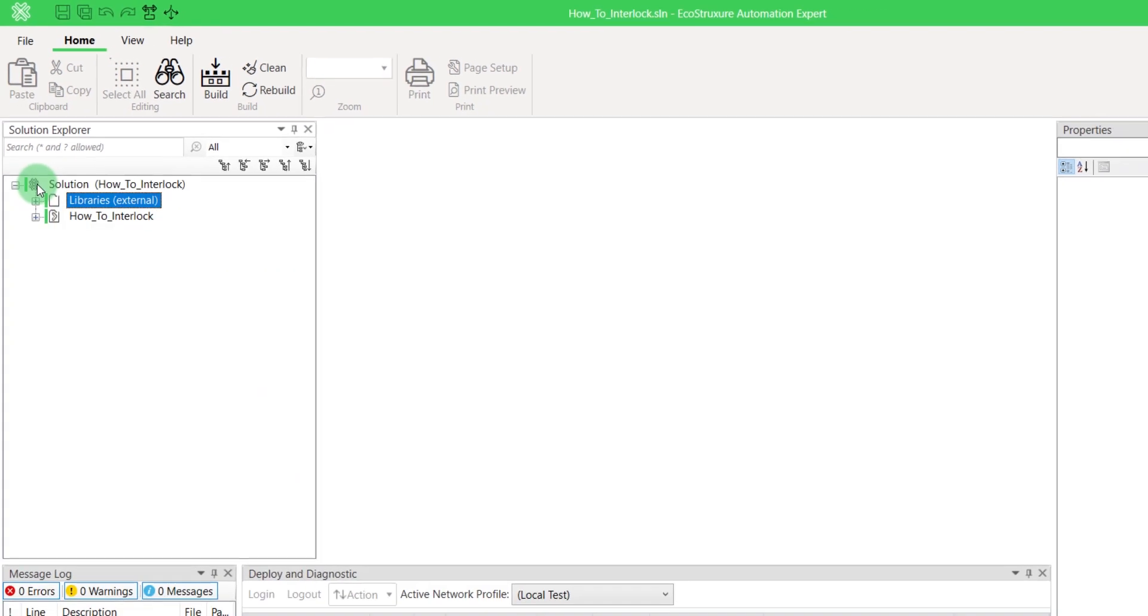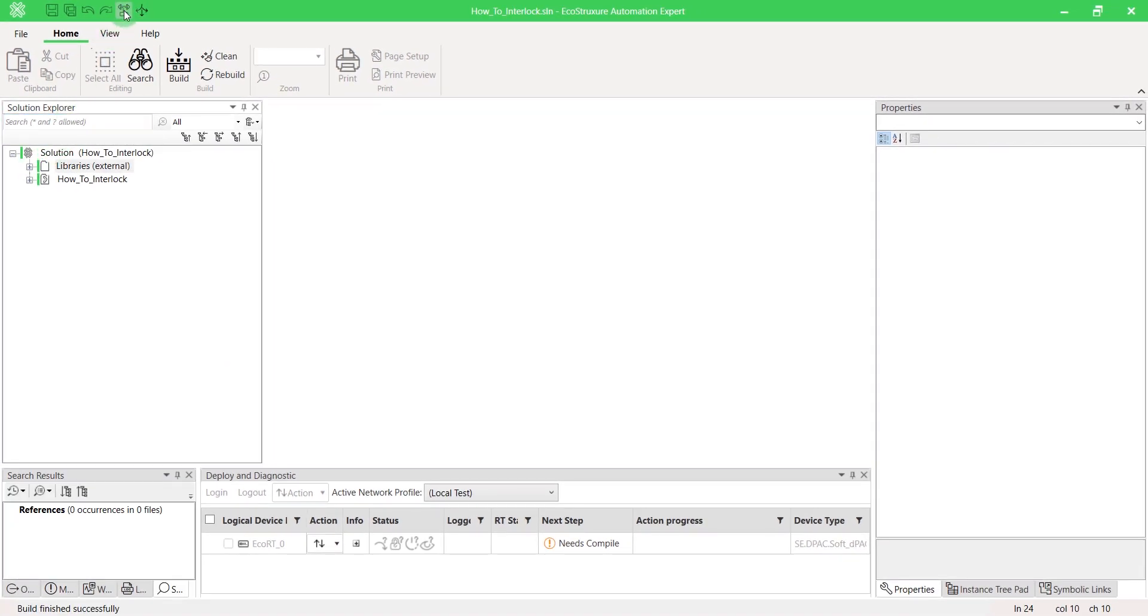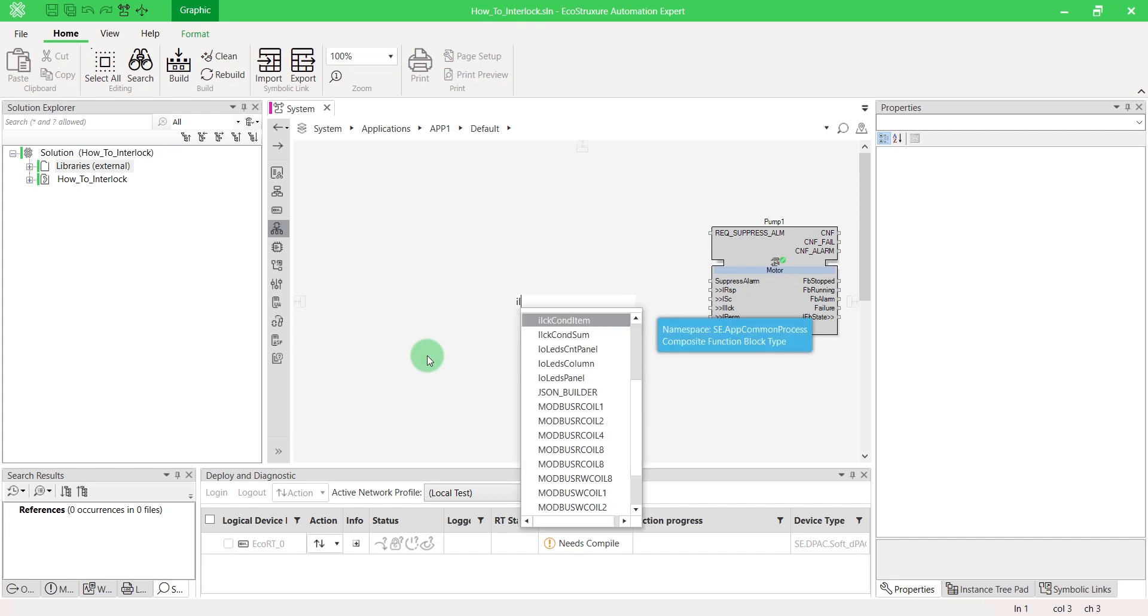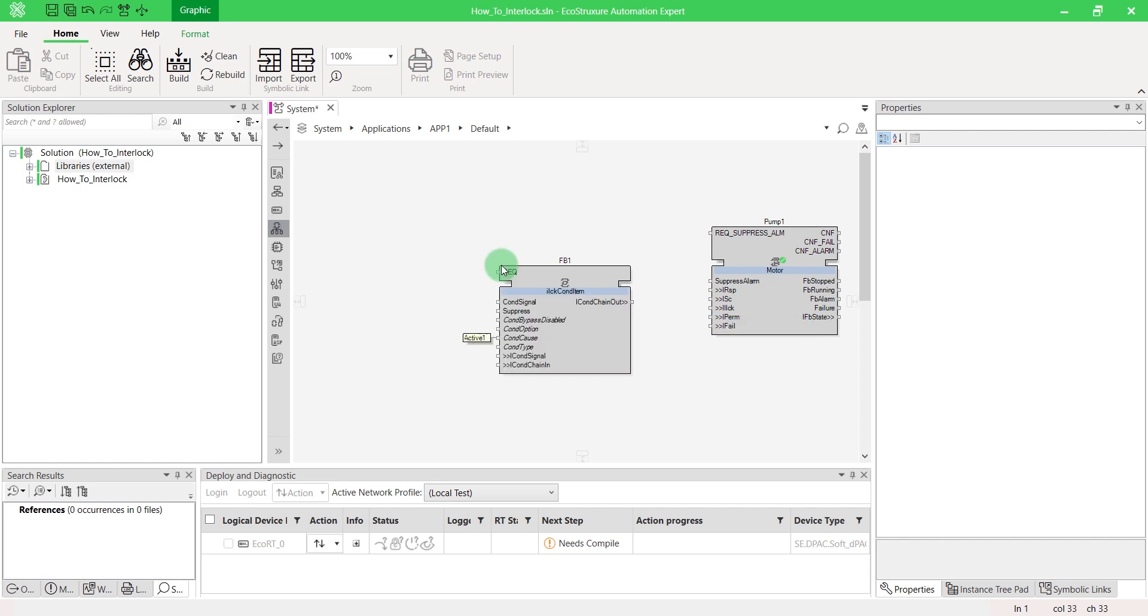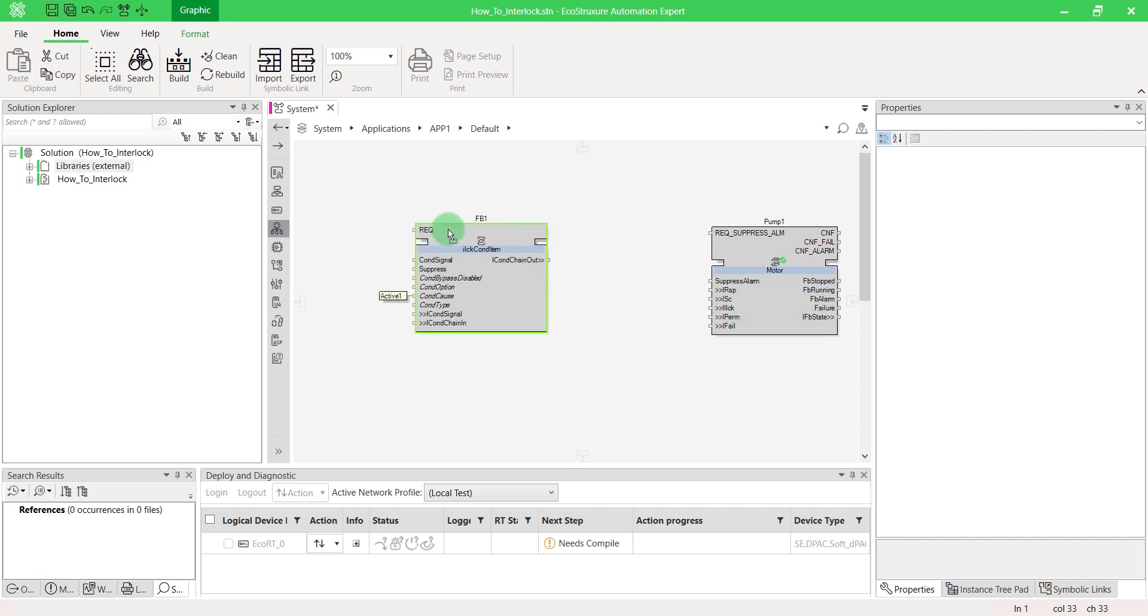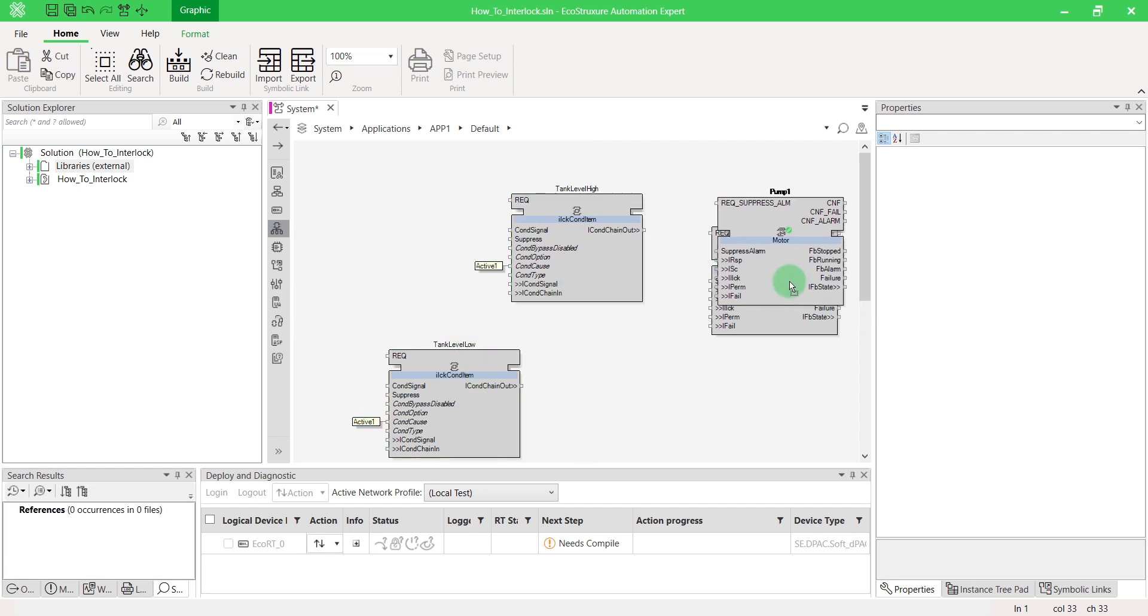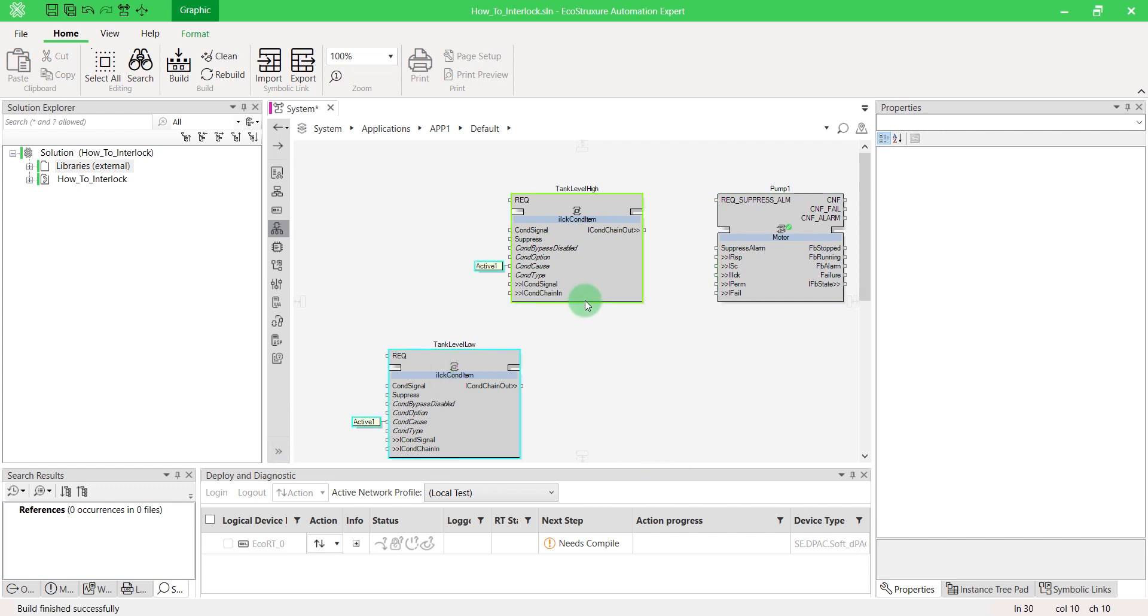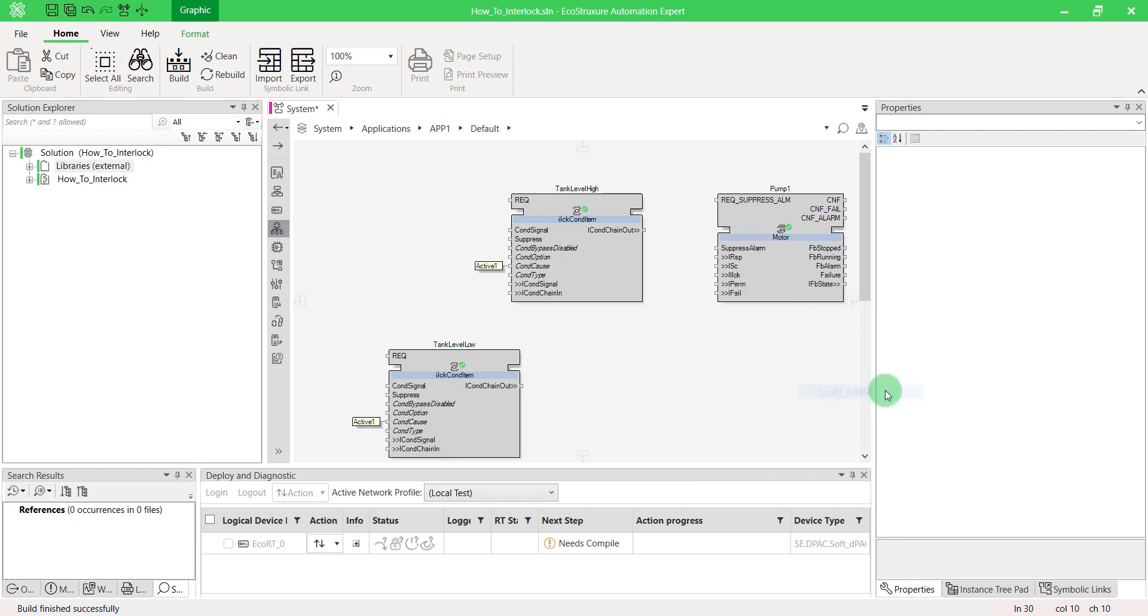For the example, we'll control the interlock of a simple motor as a pump. Press Ctrl-W to use the interlock block, Interlock Condition Item. The first one will represent the high filling condition of a tank and the second one the low state condition. As we are in simulation, we disabled feedback motors. Map all your blocks and build the solution.